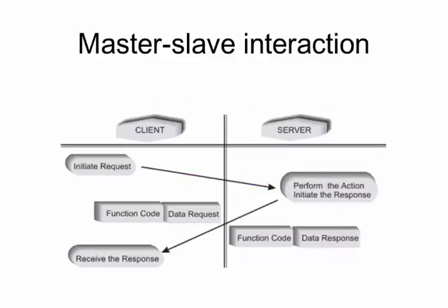As we work through it, we look at the standard packets over the network. It's a serial network, that's what we're talking about for this session. IP, next session. Your client server initiates a request. Modbus has a very discrete, small set of function codes. So it sends a function code with some data following it, which tells the server what location, how many, a few basic instructions on what's to be done with the function code that's passed over the network.